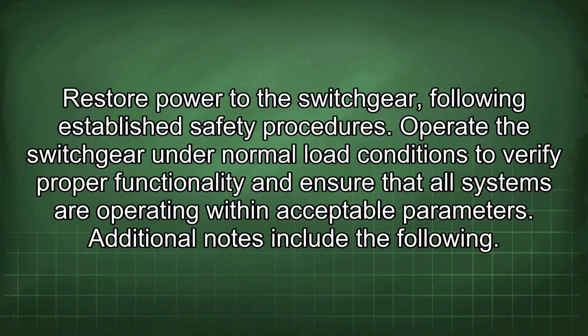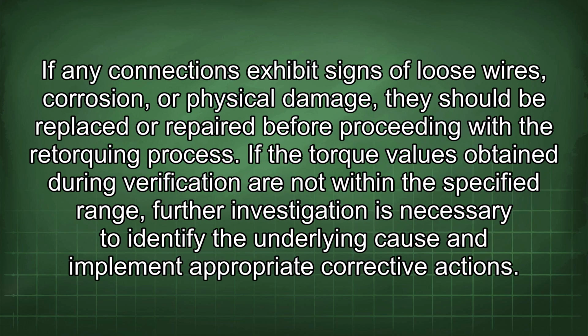Operate the switchgear under normal load conditions to verify proper functionality and ensure that all systems are operating within acceptable parameters. Additional notes include the following. If any connections exhibit signs of loose wires, corrosion, or physical damage, they should be replaced or repaired before proceeding with the retorquing process. If the torque values obtained during verification are not within the specified range, further investigation is necessary to identify the underlying cause and implement appropriate corrective actions.